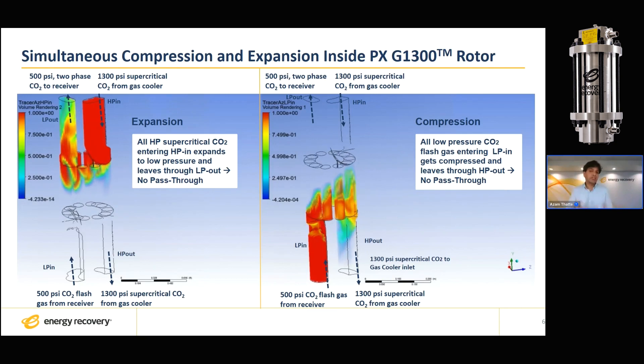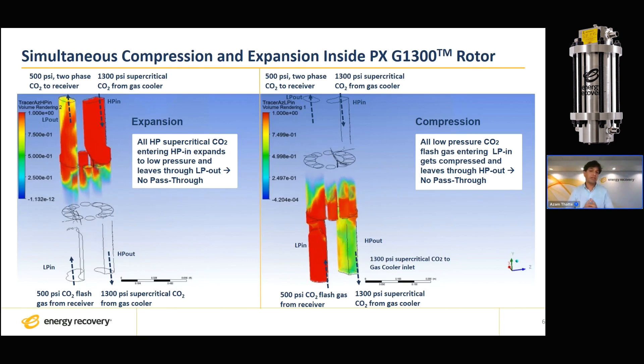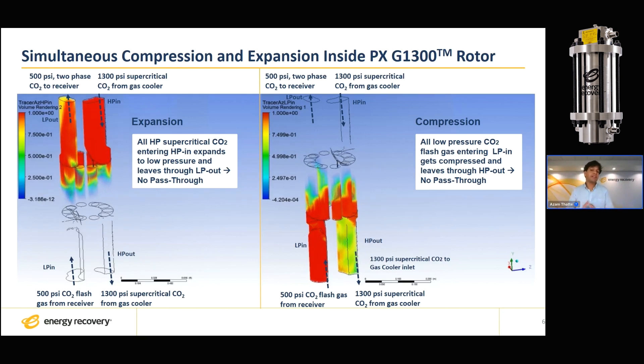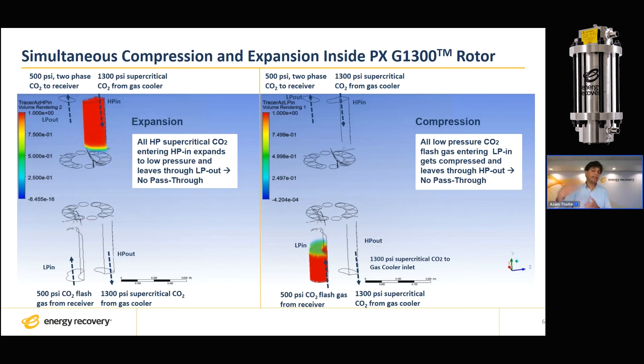In fact, the pressure exchanger is achieving this feat of free compression by using the expansion work recovery in the other half of the rotor, as seen on the left side of this animation. What you are seeing there is high-pressure supercritical CO2, maybe at around 1500 psi coming from the gas cooler exit, enters the rotating duct of the pressure exchanger. It eventually gets sealed up, and as that duct gets exposed to the low-pressure pole, there is an expansion wave that sets in and sort of isentropically expands that high-pressure supercritical CO2 into a low-pressure two-phase liquid gas mixture.